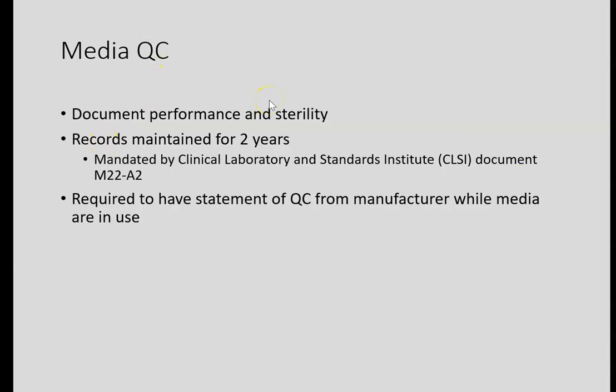Media QC: media has to be QC'd when it comes from the manufacturer. The manufacturer did the quality control testing to make sure it was working properly before they packaged it up and sent it out. But the problem is that between there and where you are, there are a whole bunch of people handling it — whether it was stored properly. So you have to then QC the media to make sure it is working properly.